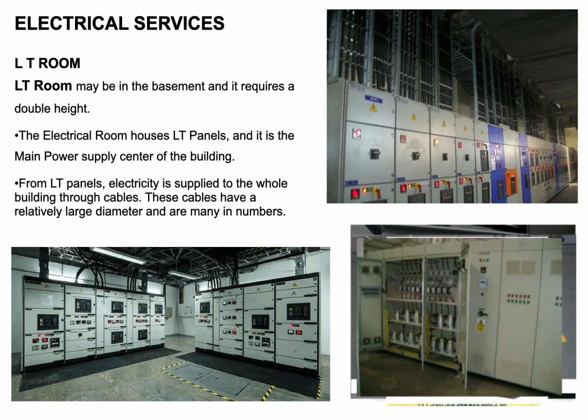The electrical room houses LT panels and it is the main power supply center of the building. From LT panels, electricity is supplied to the whole building through cables. These cables have a relatively large diameter and are many in numbers. So for the purpose of maintenance, they are not embedded in the civil works like we do in normal buildings. Either they are laid on cable trays, suspended from the ceiling, or are clamped to the ceiling.